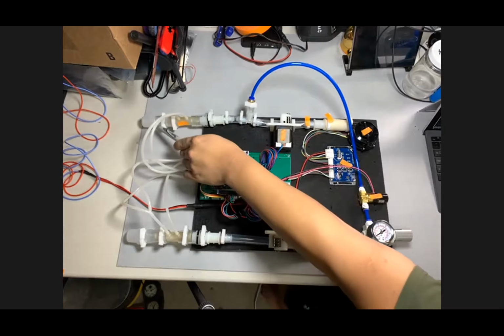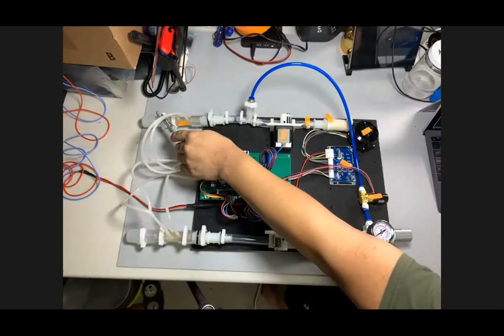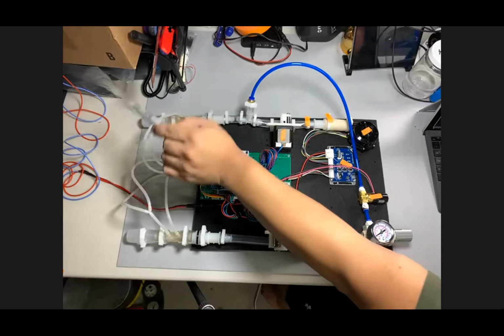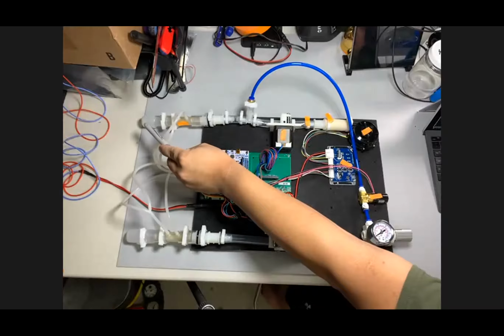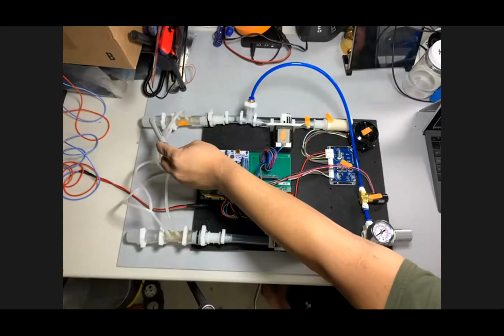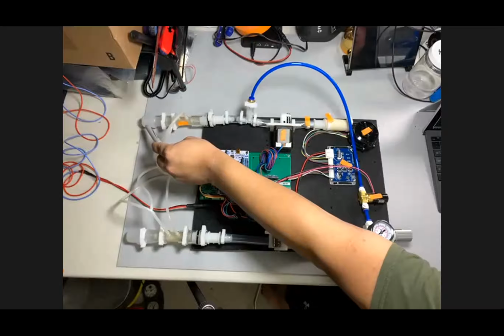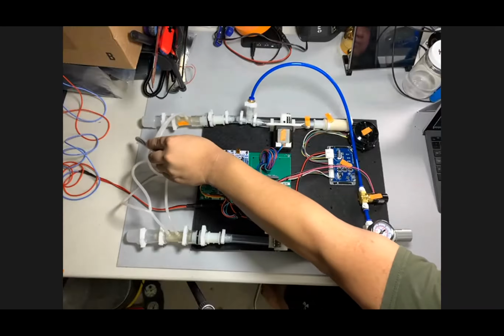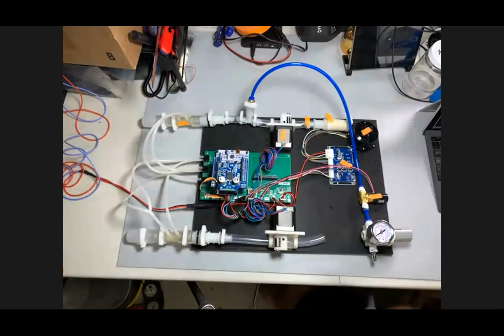This leads out to our patient adapters, the fittings that connect to the 22mm standard patient tubing. From this point onwards is hospital supplied hardware, this is our interface to the outside world. This is where the ventilator ends; it goes out to the patient tubing, to a patient T. There's either a mask, or a cannula for high flow nasal cannula, or an endotracheal tube if it's an intubated patient. Then that comes back from that T.